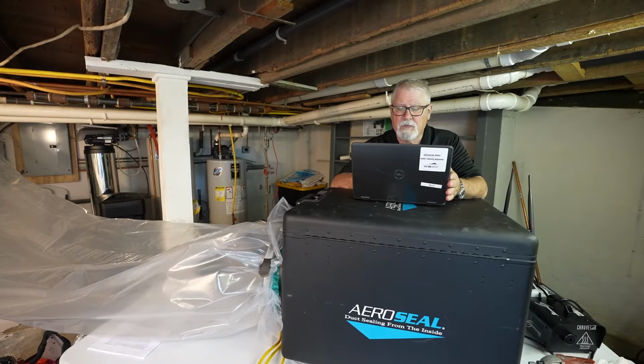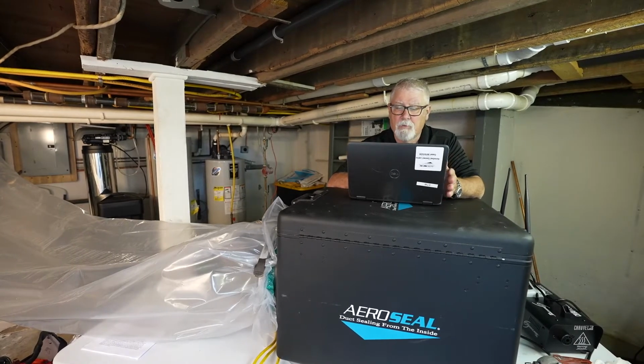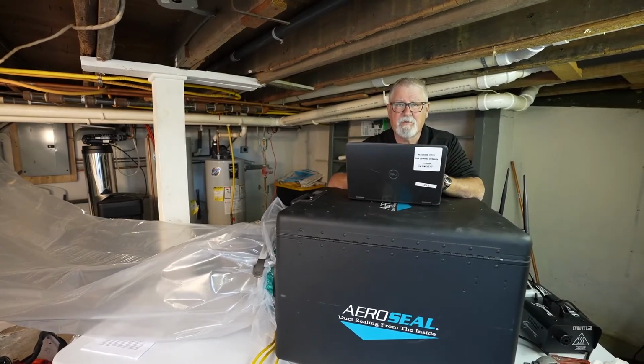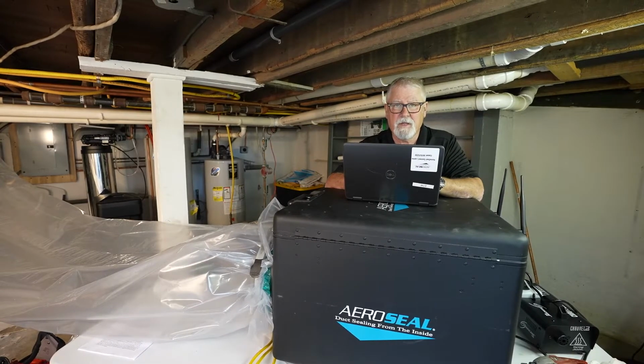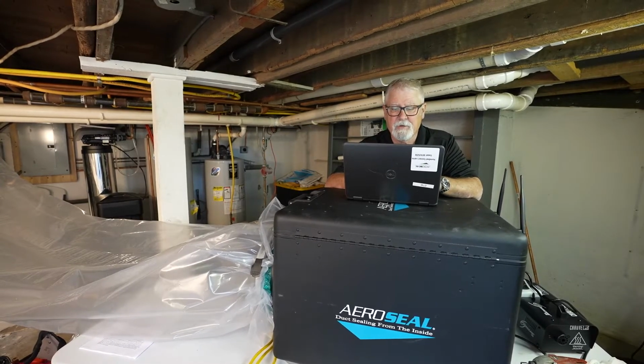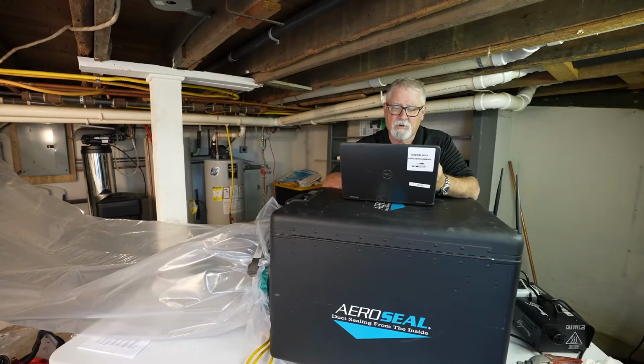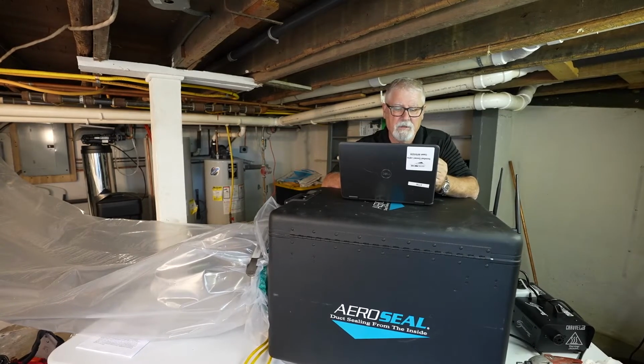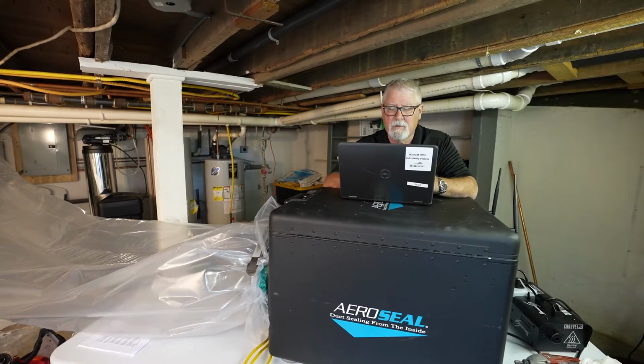We're going to start out in gate number 2. Remember, when you're doing this, I have to have a minimum fan box pressure of -4 pascals. That's a vacuum pressure. And I've got to get my duct pressure up to 10 pascals. Let's see if we can do that with just gate number 2 here.